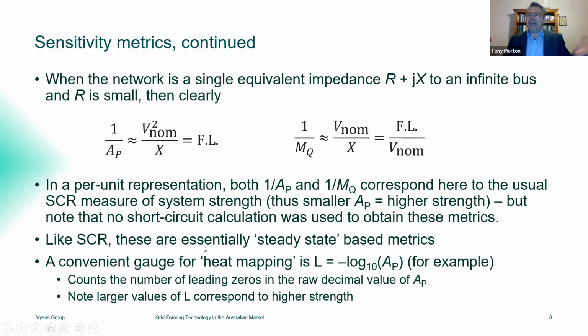So there's still basically steady state based metrics. We're not looking into any detail here on the dynamics of the network or stability studies or anything. These are just very simple numbers that we pull out of the power flow characteristics of the network with specific kinds of generation connected to it. But we can use this to get metrics of system strength across the system that aren't sensitive to the particular generation technology we're using.